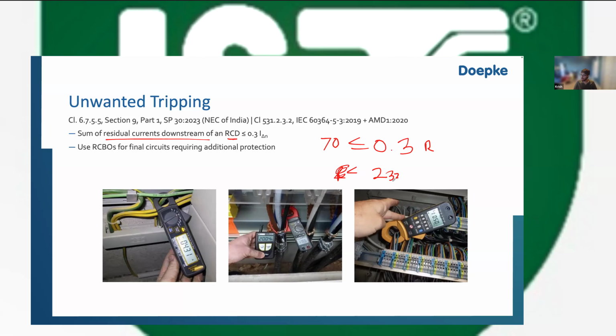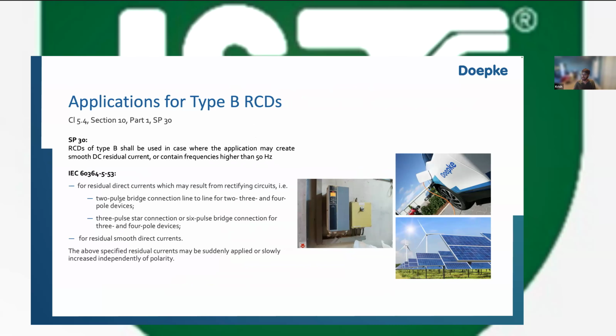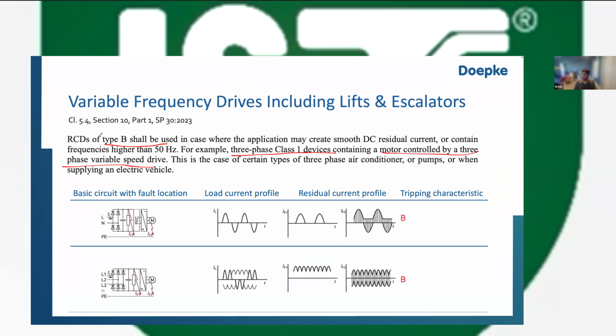So basically you need to make sure the RCD has a rated residual operating current of more than 233 milliamperes, because here we are trying to prevent nuisance tripping. Now 233 milliamperes is a non-standard size, so then you have to go to 300 milliampere. So if you use a 300 milliampere device, this is fine. What is the type of RCD to be used? Type AC, A, F, B. What is the type to use from this list? Well, you know very well that NEC says that you have to use type B in this particular case.